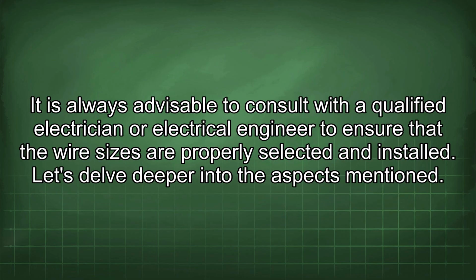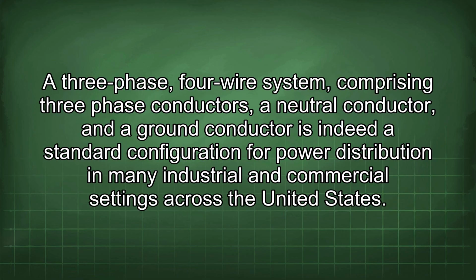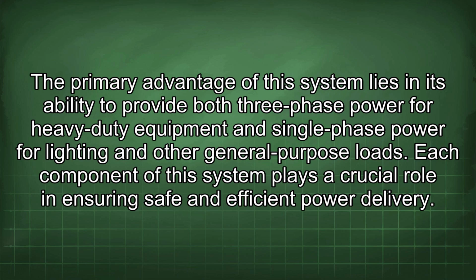It is always advisable to consult with a qualified electrician or electrical engineer to ensure that the wire sizes are properly selected and installed. Let's delve deeper into the aspects mentioned. A three-phase, four-wire system comprising three-phase conductors, a neutral conductor, and a ground conductor is indeed a standard configuration for power distribution in many industrial and commercial settings across the United States. The primary advantage of this system lies in its ability to provide both three-phase power for heavy-duty equipment and single-phase power for lighting and other general-purpose loads.